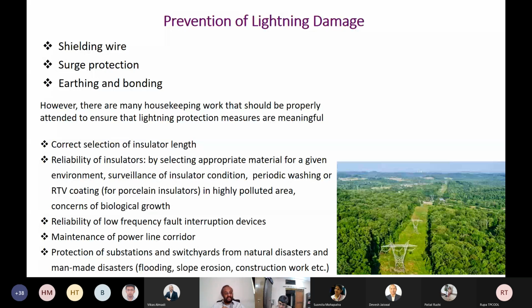Correct selection of insulator length. Okay, so before going into the lightning protection, keep your focus on whether the non-transient condition electrical safety measures have been taken correctly. So the correct selection of insulator length, even without lightning, you have to think about it. Then reliability of insulators by selecting appropriate material for a given environment. Now, for example, if you have a transmission line or distribution line in a highly polluted area, and if you have ceramic insulators, you've got to be a little careful. For example, you can have an RTV coating to prevent the degradation of the insulators.